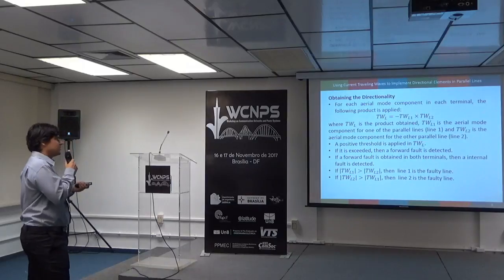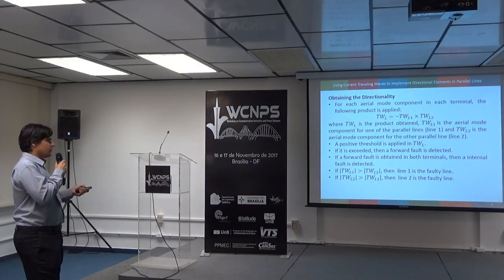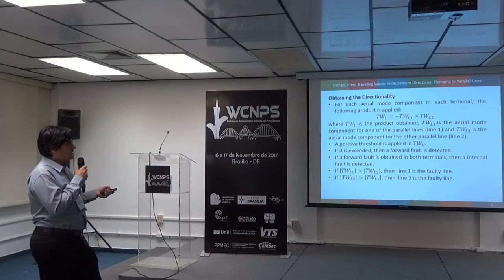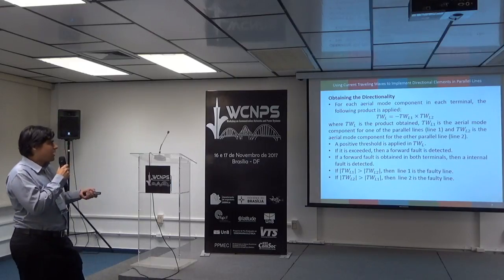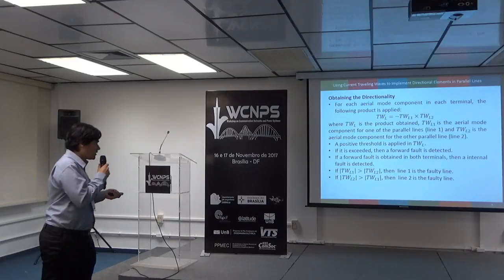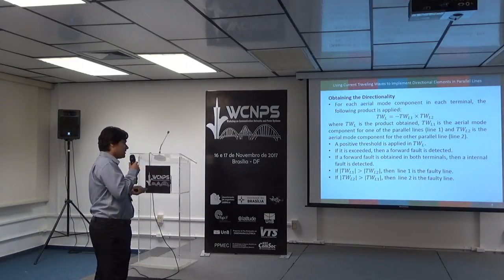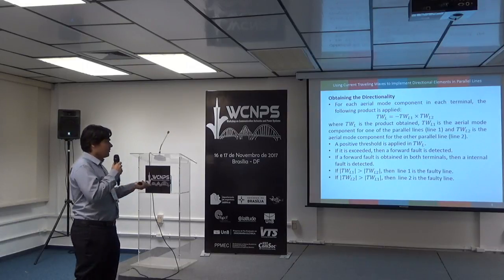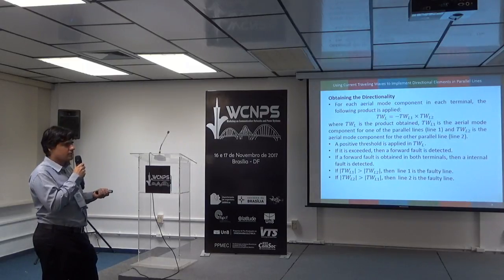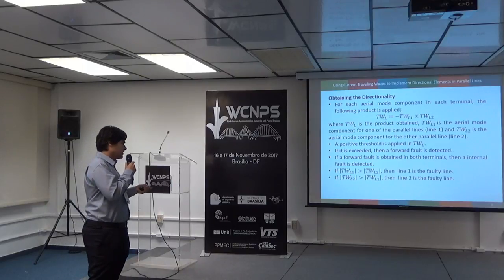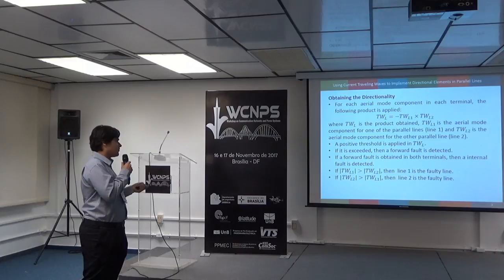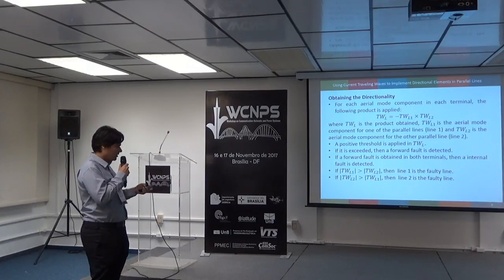Obtain the directionality. We make this product. The product is, we put a negative sign for choice. And the TWL is the product obtained. TWL1 is the aerial mode component for one of the parallel lines, line 1, we call. TWL2 is the aerial mode component for the other parallel line, line 2, we call. A positive threshold is applied in TWL. If it's exceeded, then a forward fault is detected. If a forward fault is obtained in both terminals, then an internal fault is detected. If an internal fault is detected, we make this comparison with the absolute values of TW1 and TW2. The greater, you indicate the fault line.